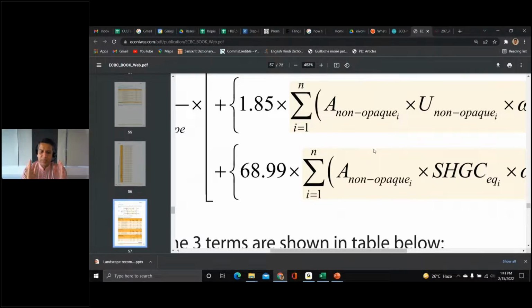SHGC is a very important component, which is why in the calculation you see 68.99 into area of the non-opaque, which is the glass, into the SHGC of the glass, into the orientation factor.